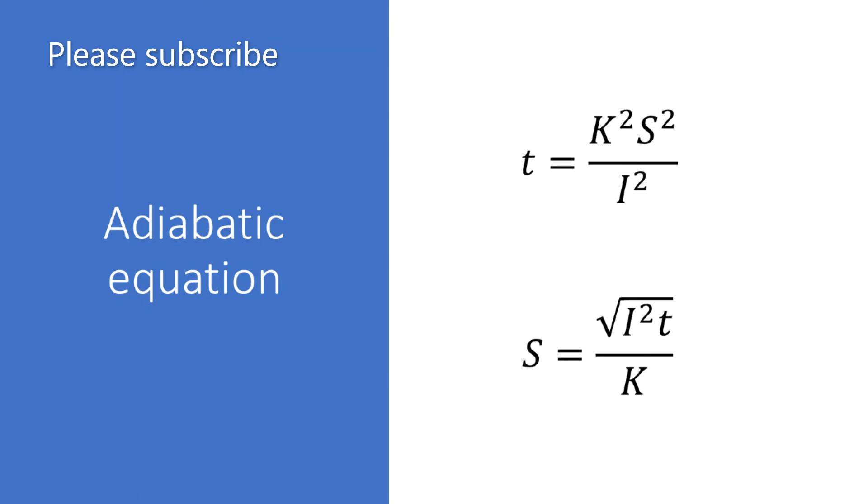In the second equation S equals the square root of I squared multiplied by T divided by K is for the minimum size CPC. So we plot the fault current on the time current characteristics to find the time and then we can carry out the equation.